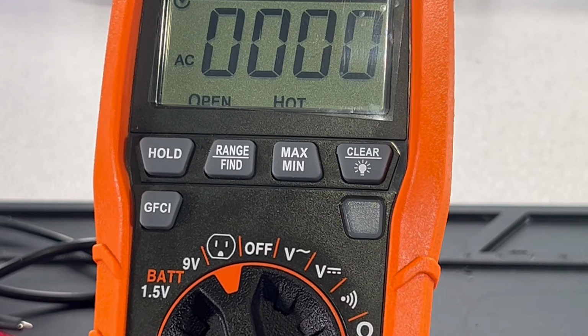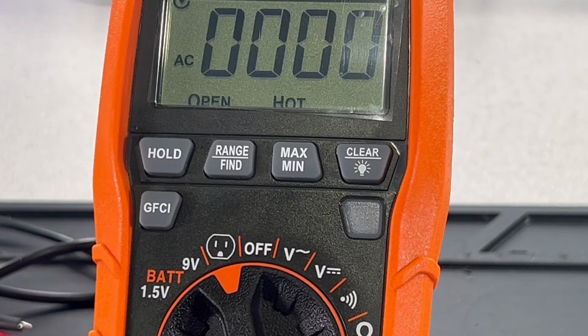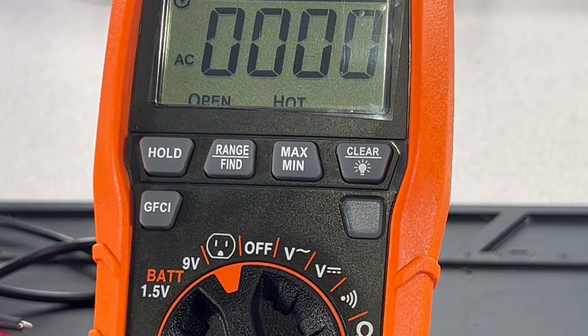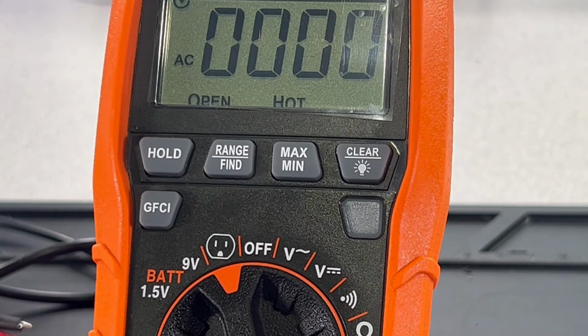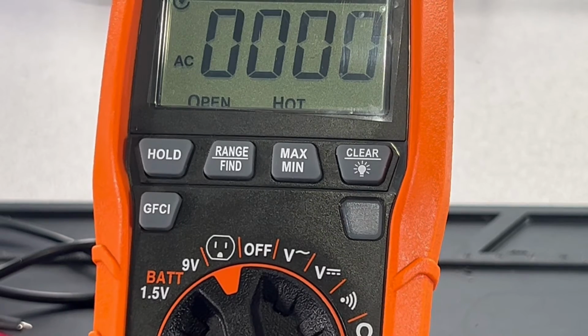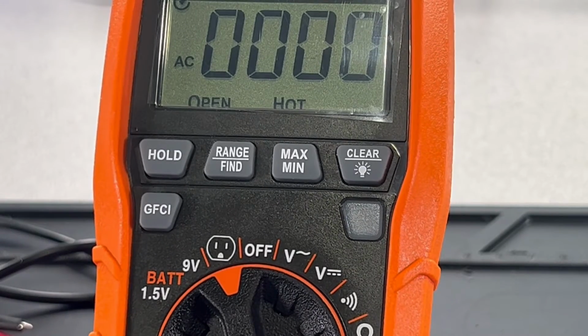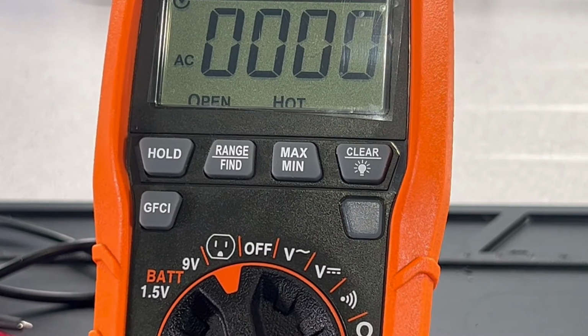As far as testing GFCIs, the standard trip current is either 6 milliamps or up to 9 milliamps, depending on what brand you're using. Excuse me, I'm drinking a cup of coffee here. This one also, when you're testing a GFCI, puts out 6 to 9 milliamps to trip the GFCI. It's really nice. I don't have anything bad to say about this.